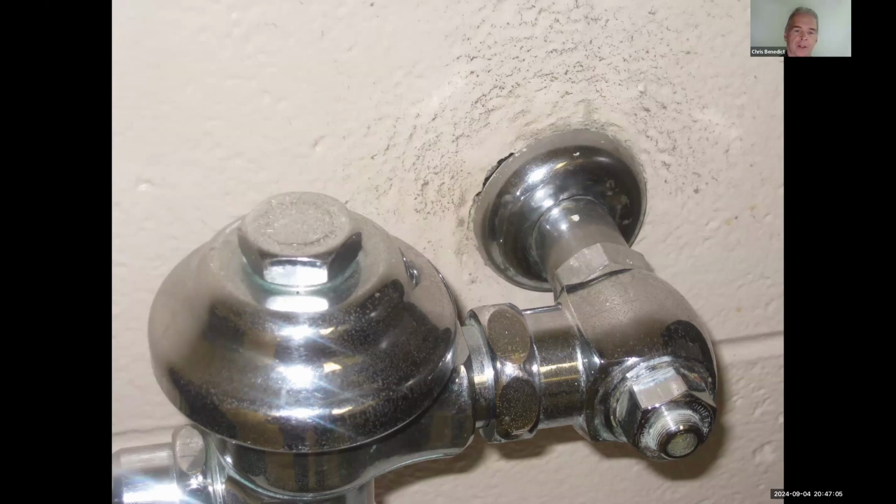But air is leaking all around, and the air goes across the bumpy wall and leaves dirt behind. So this dirt is the tell that you can see with a visual inspection. It's a tell that air is leaking through that hole. And for a lot of hours of the year, it's been leaking out of that hole.